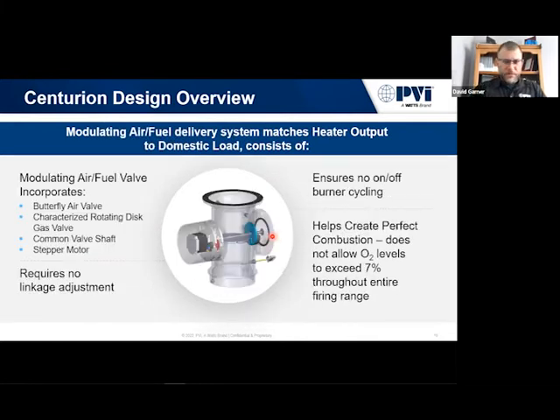The air fuel valve, this is a new technology to PVI, but this is what allows us to have that 20-to-1 turn down and maintain a proper combustion level throughout the entire turn down range. One of the problems you have with the blower is once you start slowing it down, you get to the point to where the blower is turning, but you're just not moving any air, and that's about a 6-to-1 turn down ratio.